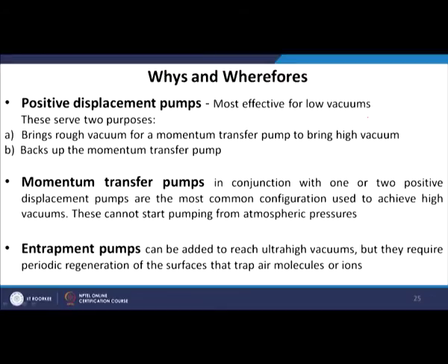Now, the positive displacement pump is the most effective for low vacuums. They serve two purposes. First, they bring rough vacuum, and for a momentum transfer pump that brings high vacuum, they back up the momentum transfer pump.